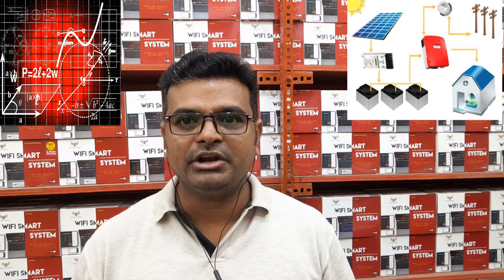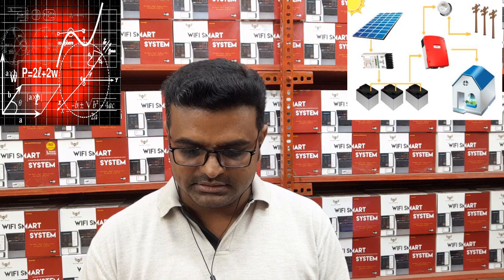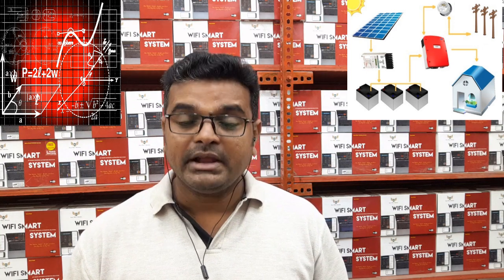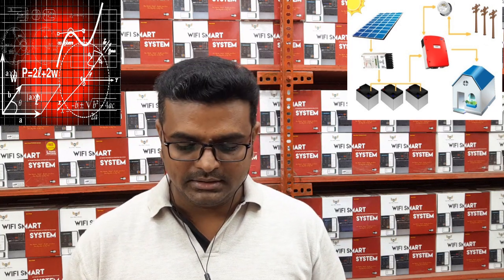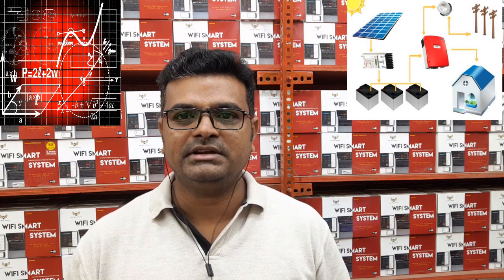For that, you need to go with solar panels — I have considered poly-crystalline, not mono-crystalline. Mono-crystalline has a little higher efficiency compared to poly-crystalline. For this system, it comes to almost 1900 Wp of panels required, using poly-crystalline panels, with all energy losses and design factors considered.